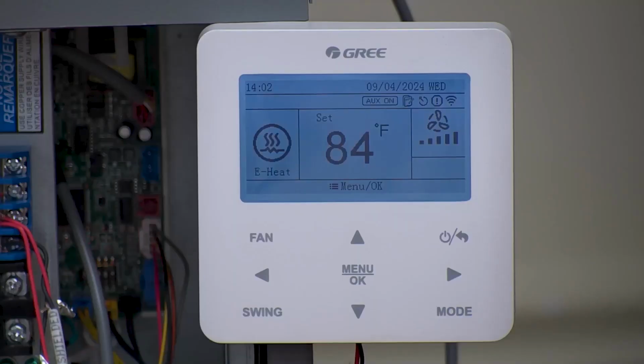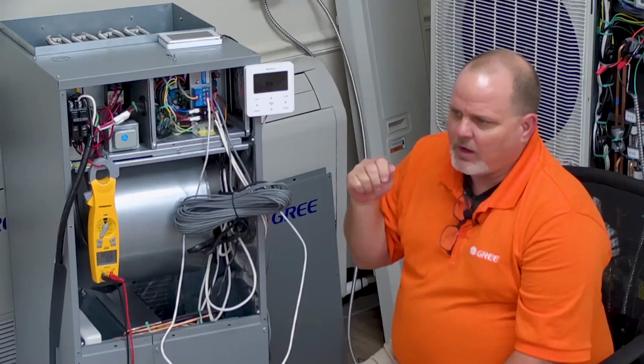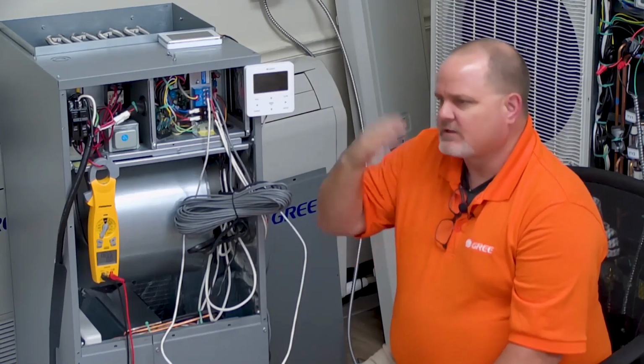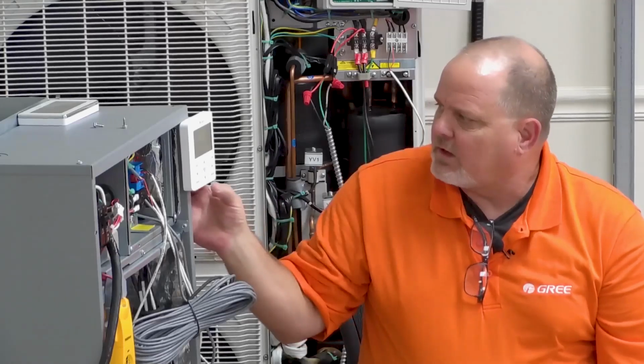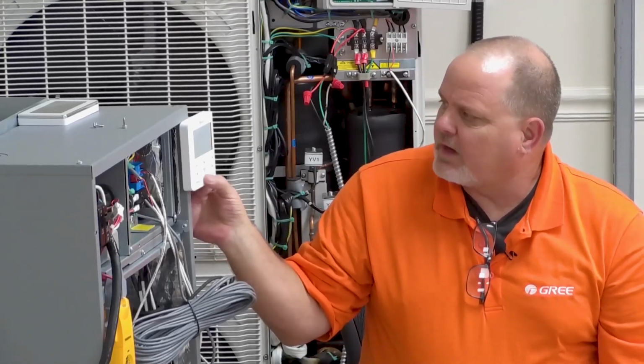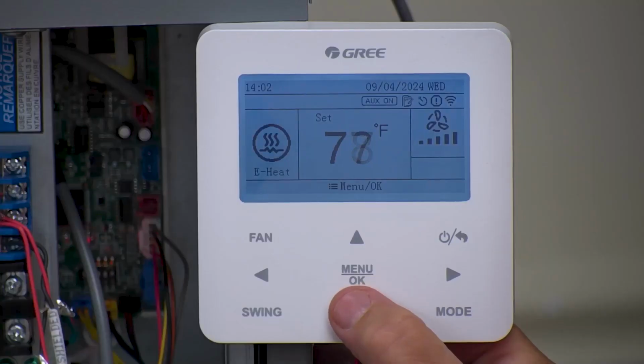There we go. She's on. As I said, it shows auxiliary on. So I didn't time that, but I would say it's probably close to 5 minutes. Now I didn't time it, it's got to be at least 5 minutes off, because as you've seen when I first did it, electric heat came on right away. But once you cycle it off, it cycles back on, it's going to have a 5-minute delay. So now I'll run this back down. We should be able to lose our auxiliary heat call.